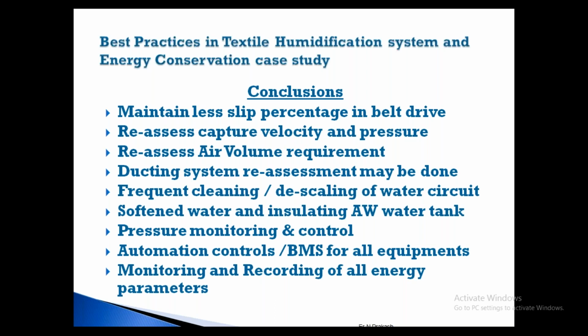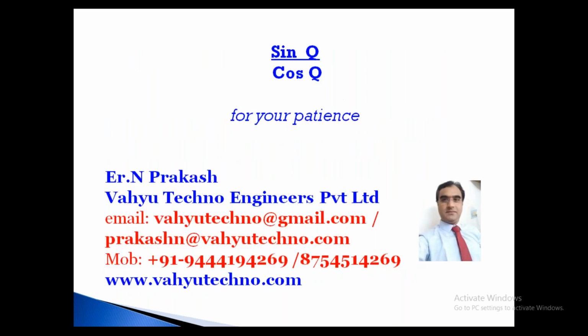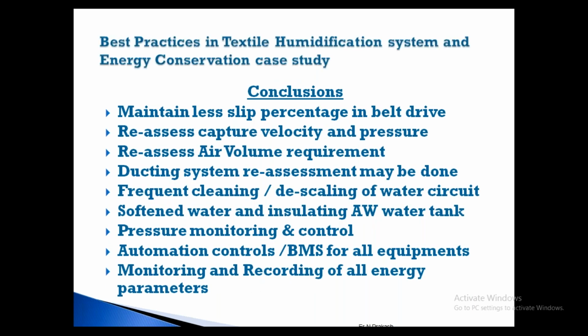So pressure monitoring and control system, automatic control system, and how the building management system is done, this is one big subject. One day we have to talk about automatic control, how automation is to be done in the plant, particularly the HVAC humidification system. Then monitoring and recording of all energy parameters, as I told, for each and every individual motor, what was the power factor, what was the frequency, for each and everything we have to collect information. That is not assumption. They will tell over the phone after they do the visit, they ask what was the power factor, what was the voltage, like that. We have to read it, then we will find out easily.